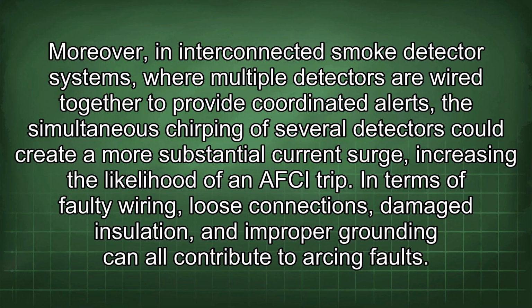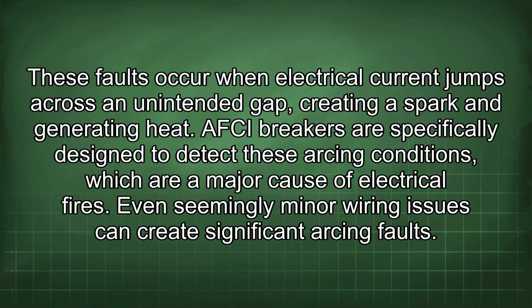In terms of faulty wiring, loose connections, damaged insulation, and improper grounding can all contribute to arcing faults. These faults occur when electrical current jumps across an unintended gap, creating a spark and generating heat.